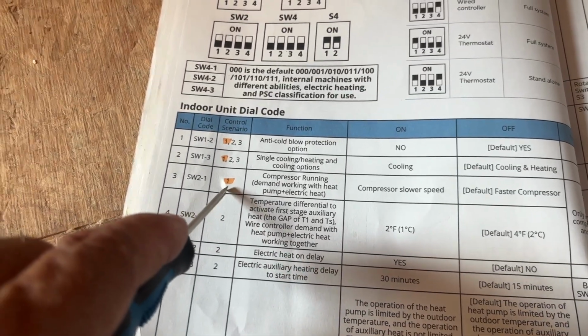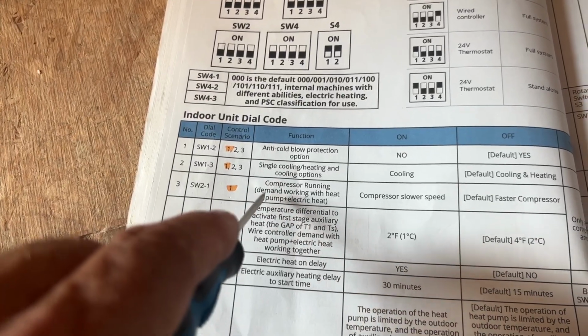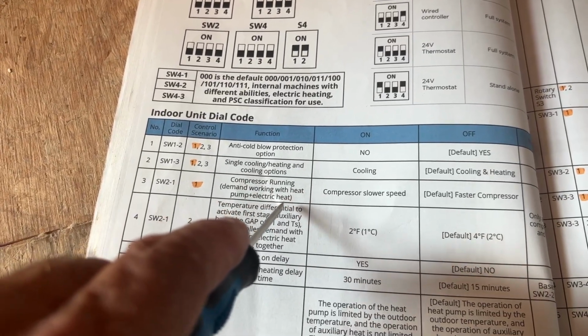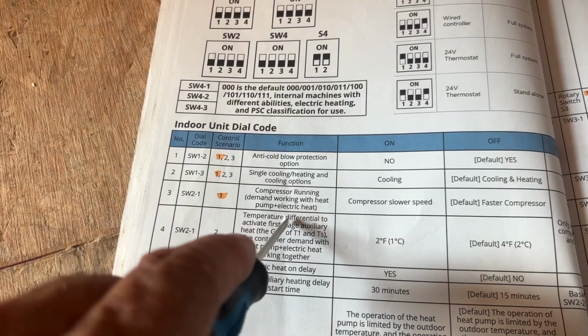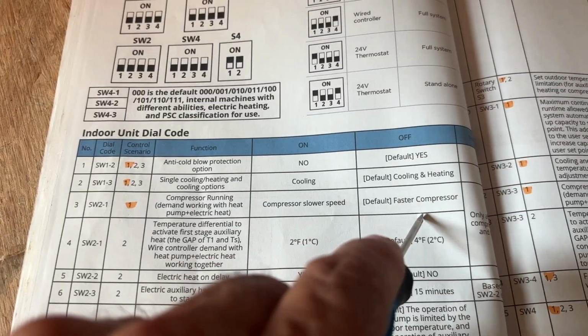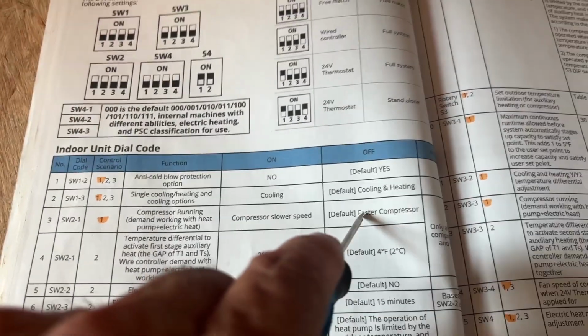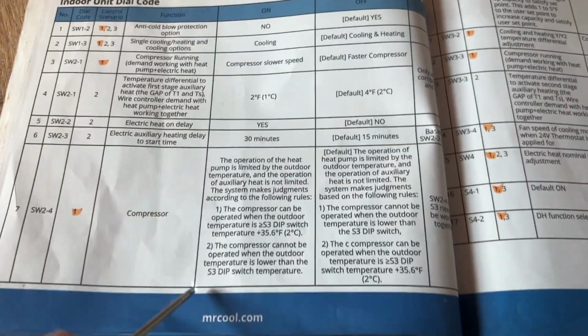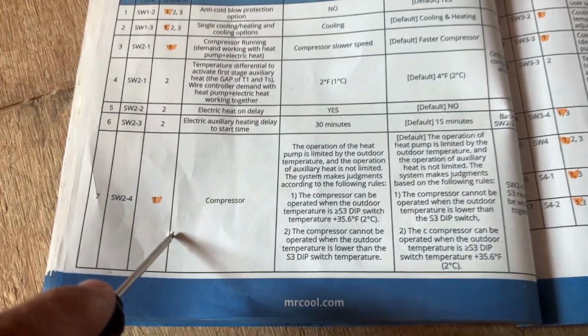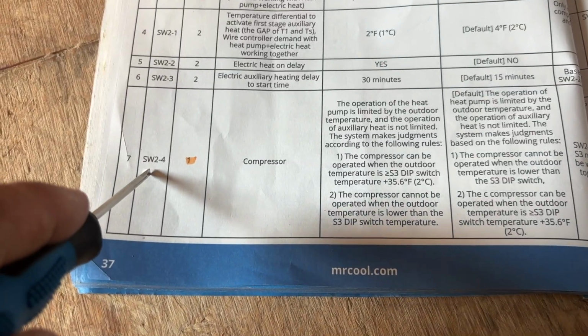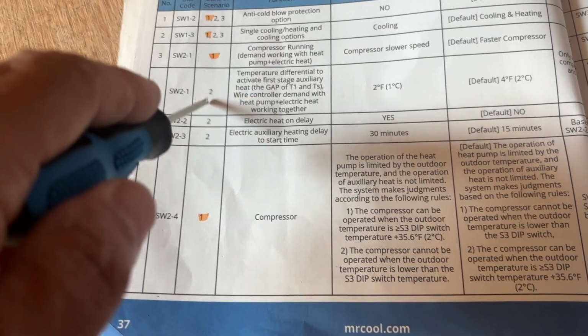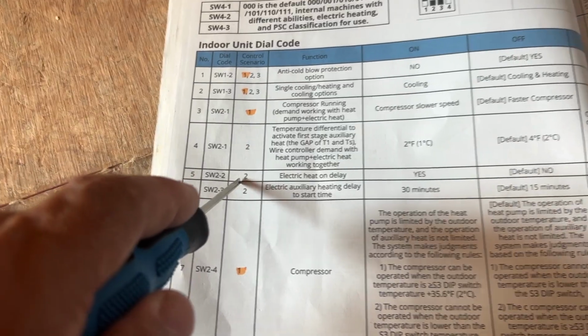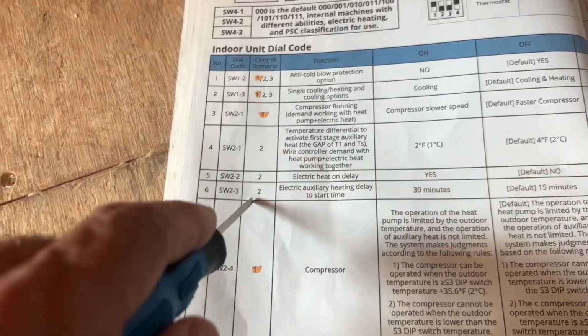SW2-1, that's control scenario 1, which is me. Compressor running, demand working with heat pump and electric heat. I want the compressor to run faster. That is the default setting, so we're going to leave that alone. I'm not going to use SW2-4. So you got 2.1, which is control scenario 2, 2.2, and 2.3. Those are 2s, which doesn't apply to me.